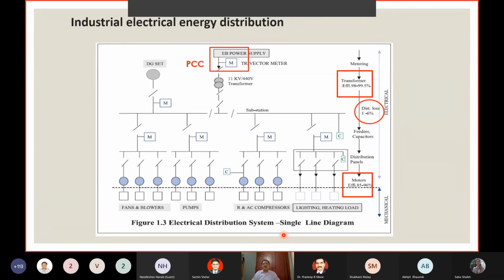For our easy understanding, I have used a very simple SLD where there is one transformer which is receiving supply from the electricity board at 11 kV and converts it into 440 volts. So the point of common coupling is very important for us as we progress; we'll be discussing this. Point of common coupling is the trivector meter. Beyond that, it is EB property; downstream of that is our property, the facility's property. So the point of common coupling is very important. We have to identify this.